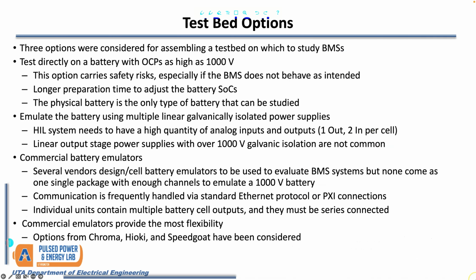For the testbed, three options were considered for our use case. The first is to test directly on the battery. This isn't a great choice, since first you carry all the safety risks I've talked about testing directly on a battery, such as thermal runaway, chance of fire, and leaking cells. Two other factors are the longer preparation time needed to adjust the battery SOC—on that graph of BMS behavior, I showed how we could instantly change the SOC with hardware-in-the-loop, but you can't do that with a real battery. You'd have to manually dissipate or recharge cells to put it out of balance before conducting your test. The last problem with testing on a real battery is that it's the only battery that can be studied.